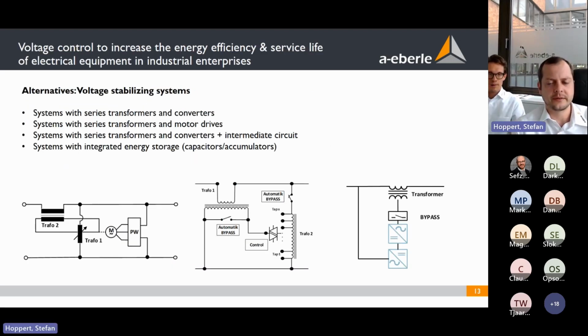So just to compare with competitors, not to compare with names, just to compare with technologies. We see there are a lot of systems existing in the market with series transformers and converters, like the right picture here, or with series transformers and motor drives, like the first picture on the left side, or with series transformers and converters in the middle, so with an intermediate circuit. And there are also systems with integrated energy storage, capacitors, accumulators, but these are more or less UPS devices. And of course, we are not comparable with UPS devices at this point.